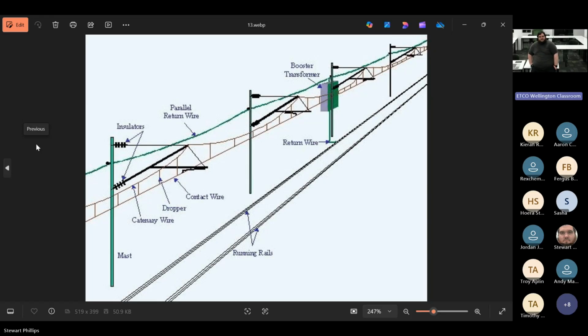In certain situations, you can use it as an earth. Hang off it with a harness. Yep. But you cannot use it as an active conductor. It has not got the required insulation to be an active conductor. Obviously, we do have uninsulated live conductors out there in the world, but they are so far off the ground that we can't touch them.